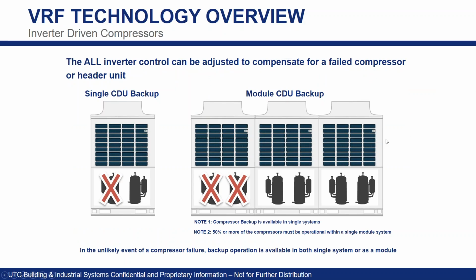This goes more into the technology here on the outdoor unit side of things. Each of our modules, right, that make up the cluster of outdoor units will have twin rotary full variable speed compressors, okay? So at all times, those compressors are going to be varying their speed. No lead lag, nothing like that. They're both variable speed. They share time, that being run time.